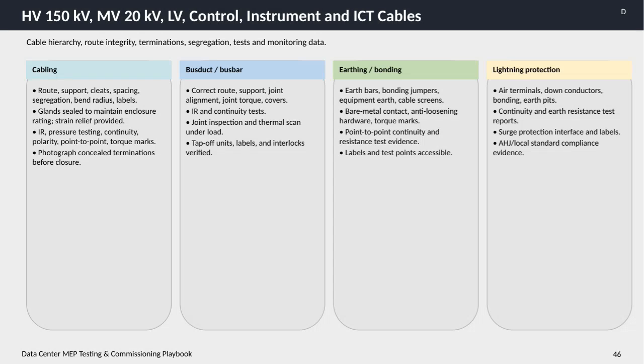Here we focus on the comprehensive testing and commissioning procedures for HV 150 kV, MV 20 kV, LV, control, instrument, and ICT cables within the data center infrastructure. Starting with cabling, it's essential to ensure proper routing, support, and spacing to maintain system integrity. We verify that cleats are correctly installed, segregation is maintained to prevent interference, and bend radii are within acceptable limits. All cables must be clearly labeled. Glands need to be sealed properly to preserve enclosure ratings, and strain relief must be provided to avoid mechanical stress.